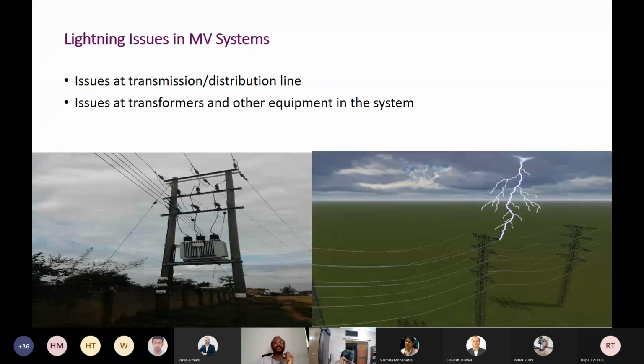Then the other one is issues at transformers and other equipment in the system. So issues at transmission and distribution line, I mean, if a lightning strikes a line, say a distribution line, what would be the consequences? This is one thing that we are concentrating on. The other thing is, if this transient goes into a transformer or substation, what would be the result?